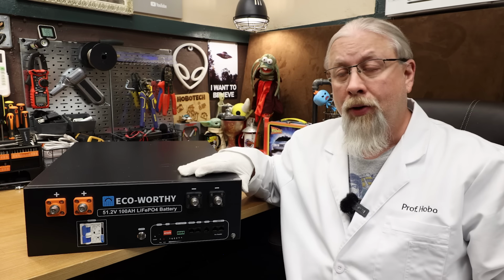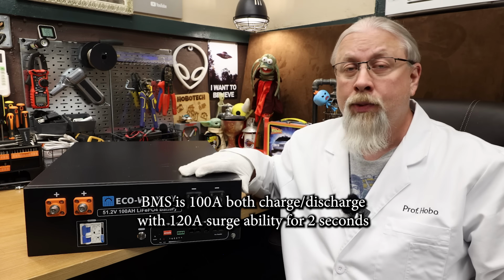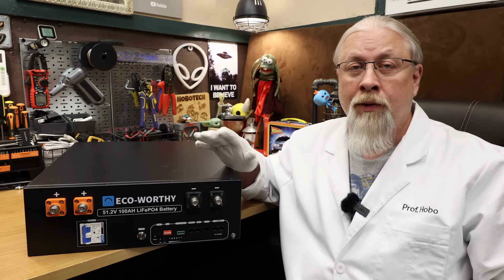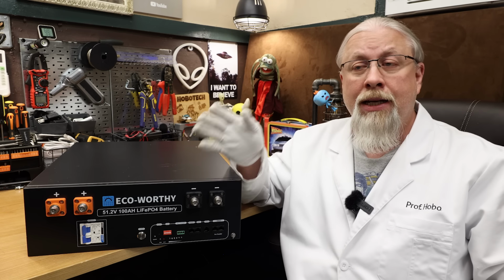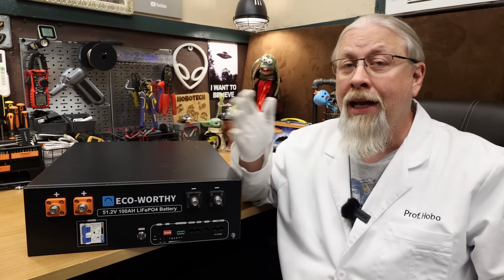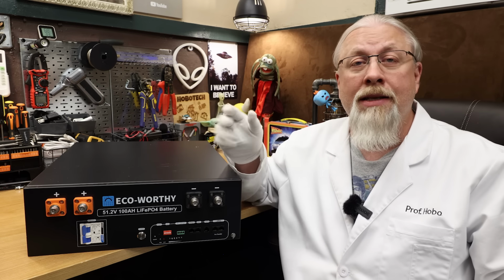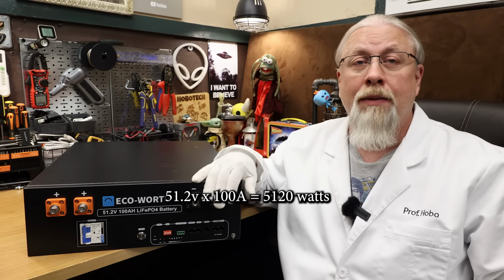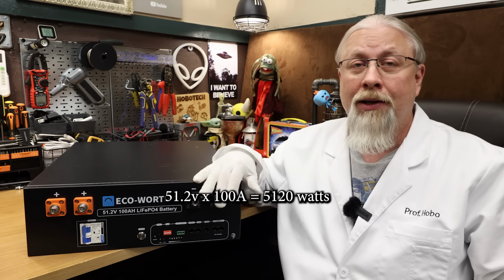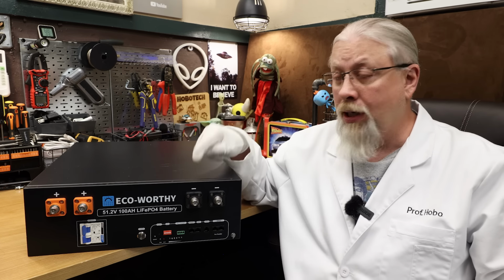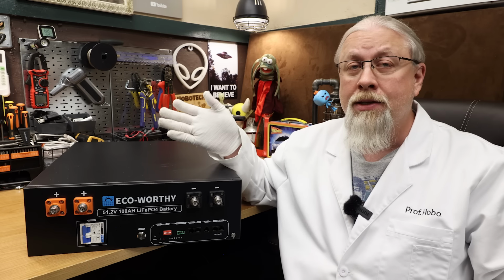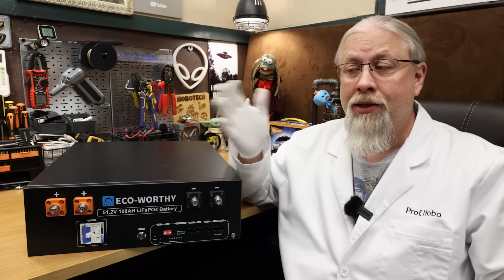This has a built-in BMS, or battery management system, rated at 100 amps for both charge and discharge. At 51.2 volts, since you take volts times amps, that equals watts, so this can handle over 5,100 watts of both charging and discharging per battery in parallel. So if you have a 5,000 watt inverter, you only need one of these batteries. If you have a 10,000 watt inverter, you'd need 2 batteries, and so on.